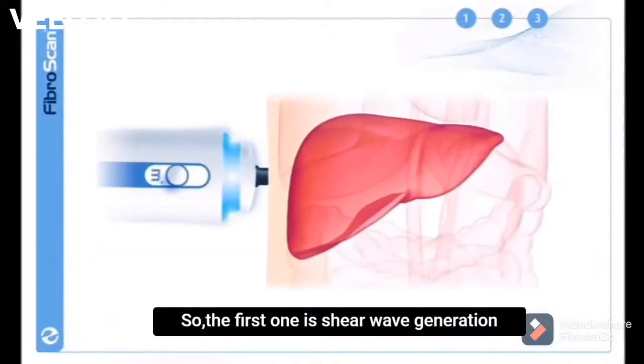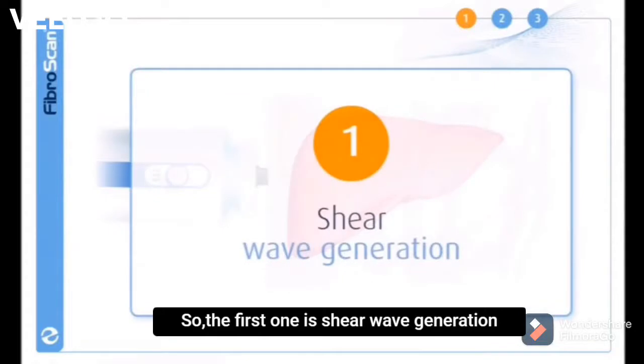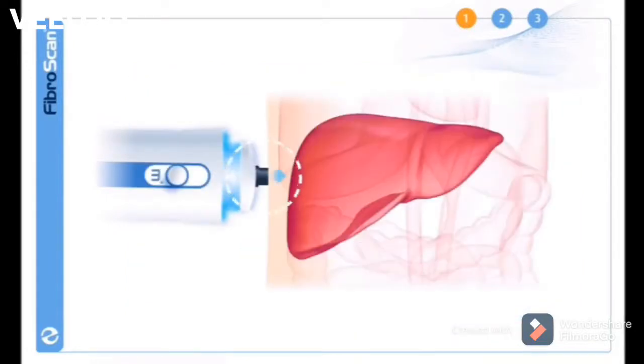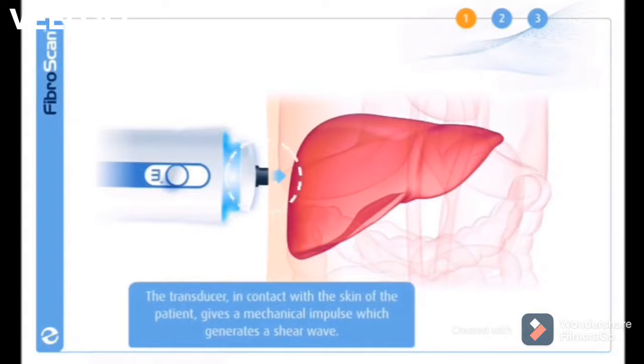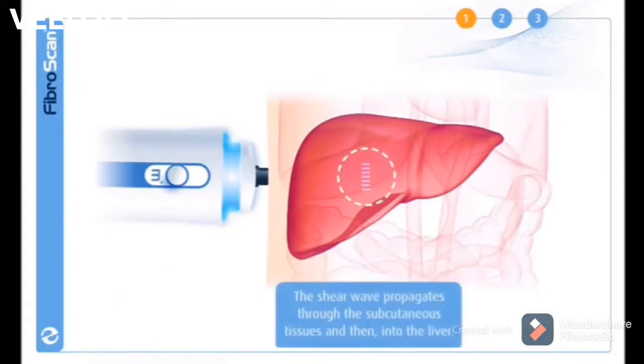Next, there are 3 steps of Fibroscan's examination. The first one is the shear wave generation. The second one is the action of the probe's ultrasonic transducer, and the third one is the calculation of shear wave speed and equivalent stiffness. So, the first one is the shear wave generation. The transducer in contact with the skin of the patient gives a mechanical impulse which generates a shear wave. The shear wave propagates through the subcutaneous tissue and then into the liver.